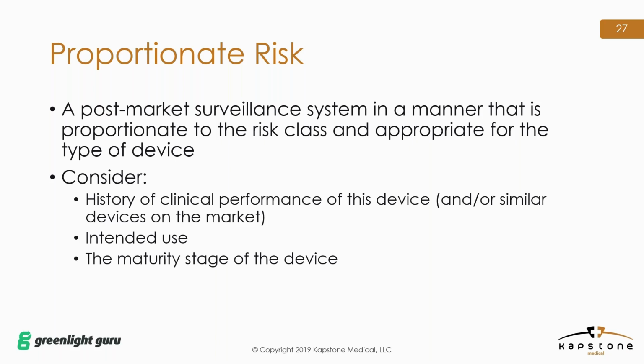So you need to develop a method on how to differentiate your risk class, and this should be included in your post-market surveillance procedures. And then specific considerations and resulting requirements can be detailed in your post-market surveillance plan for that specific device. So the types of things that you need to consider when you're differentiating according to risk is the history of the clinical performance of this device or similar devices on the market, the intended use of the device, which links directly to classification in most cases, and then of course the maturity stage of the device. So these are just the types of things that you can consider as part of integrating into your procedures.